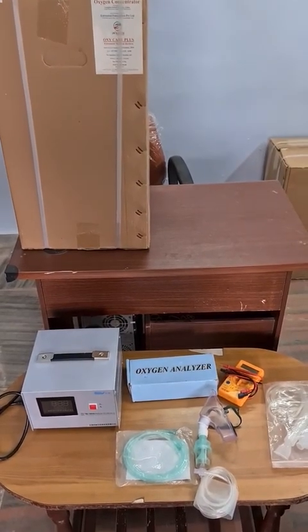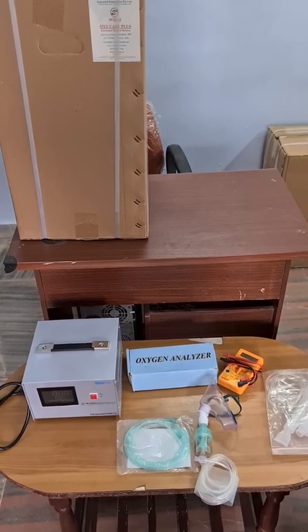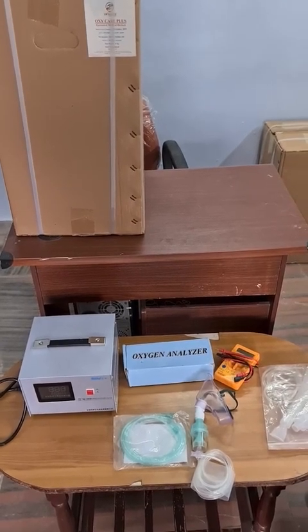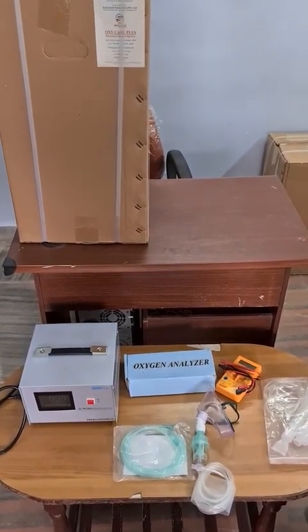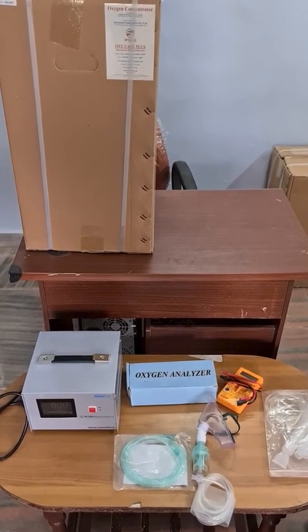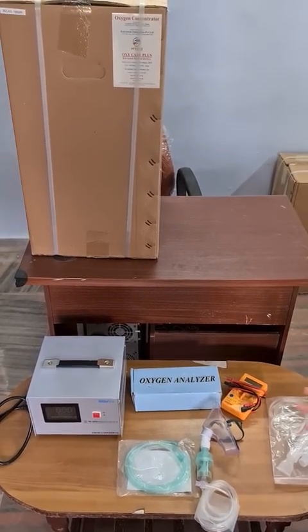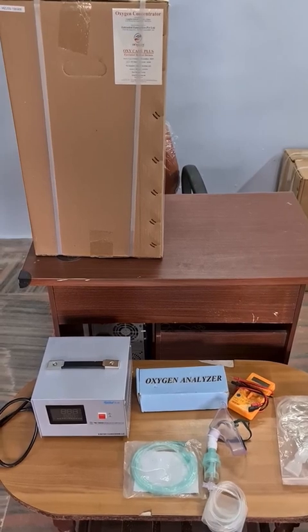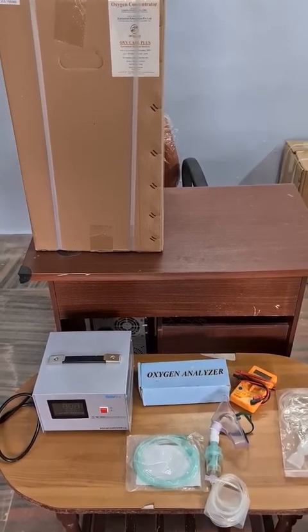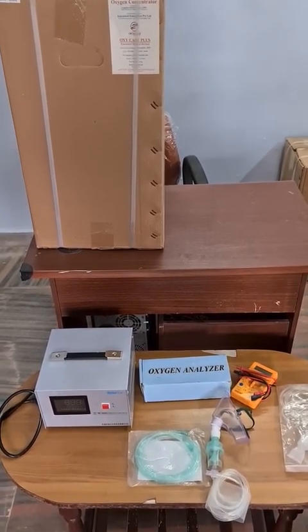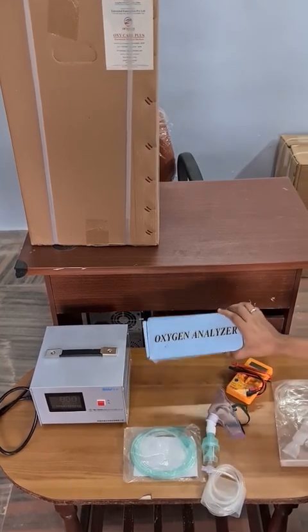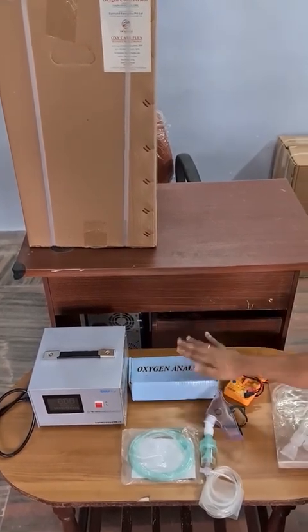The advertised purity for our concentrator is 93% plus or minus 3%. The plus or minus 3% is for altitude compensation. For example, if you take the concentrator to a higher altitude, the purity may drop by 3%. That's why it is mentioned as 93% plus or minus 3. This is a laboratory equipment which is not for sale.